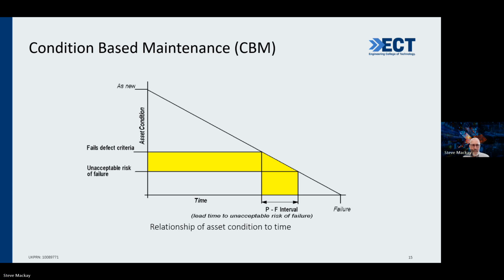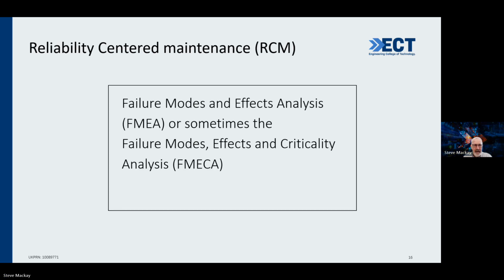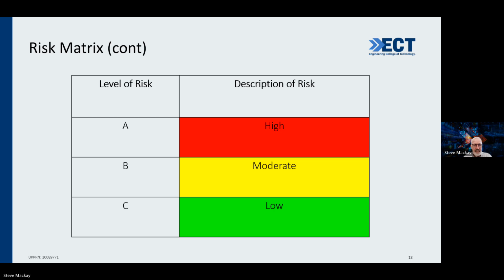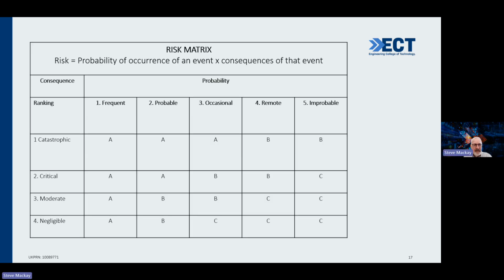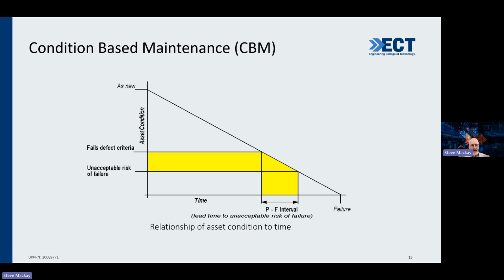Condition-based monitoring, where would you do that? And what is the difference in that and obviously reliability-centered maintenance? Any suggestions? So obviously condition-based monitoring, you're looking at a particular condition. So in the old days, and some of you may still dimly remember them, you had time-based maintenance, which is when the conveyor breaks or when the switchgear breaks, then you go and replace it. Or when you see a fault happening, you go and look at things then. Condition-based maintenance is actually about monitoring things to nail the problem before the actual bit of electrical equipment fails. So that's obviously quite important.